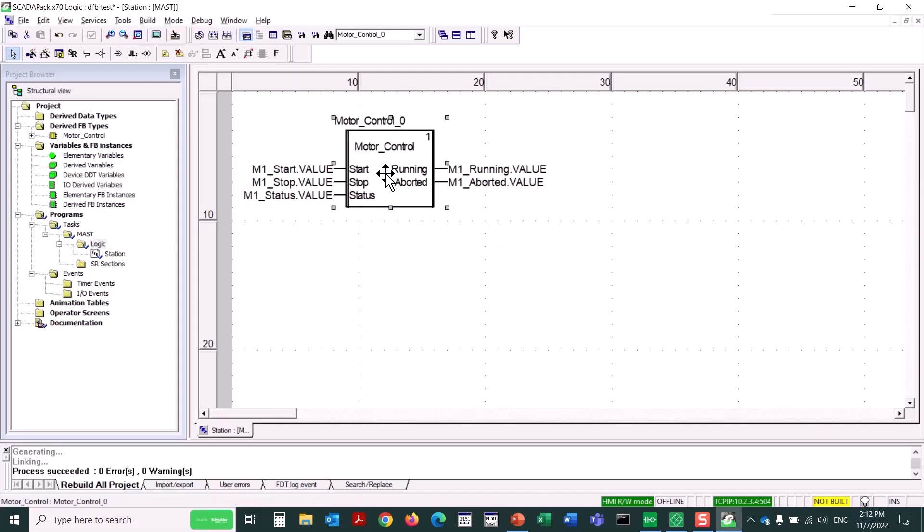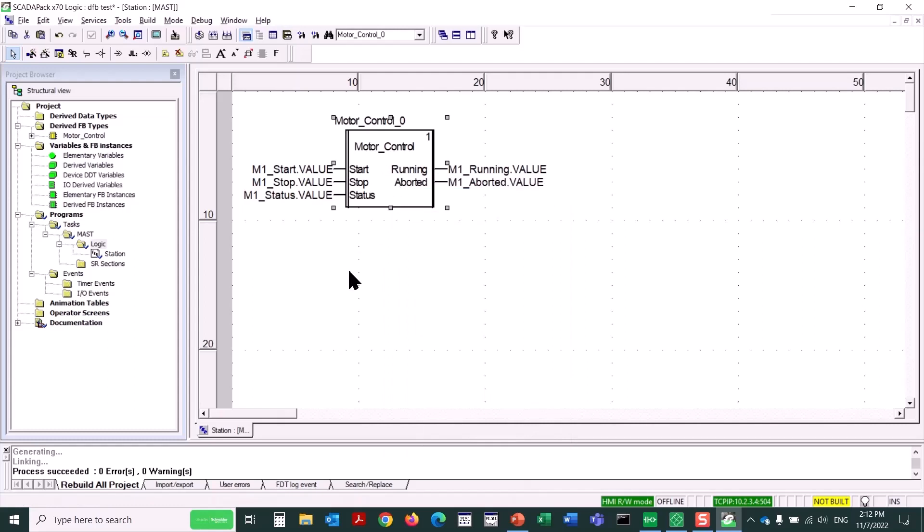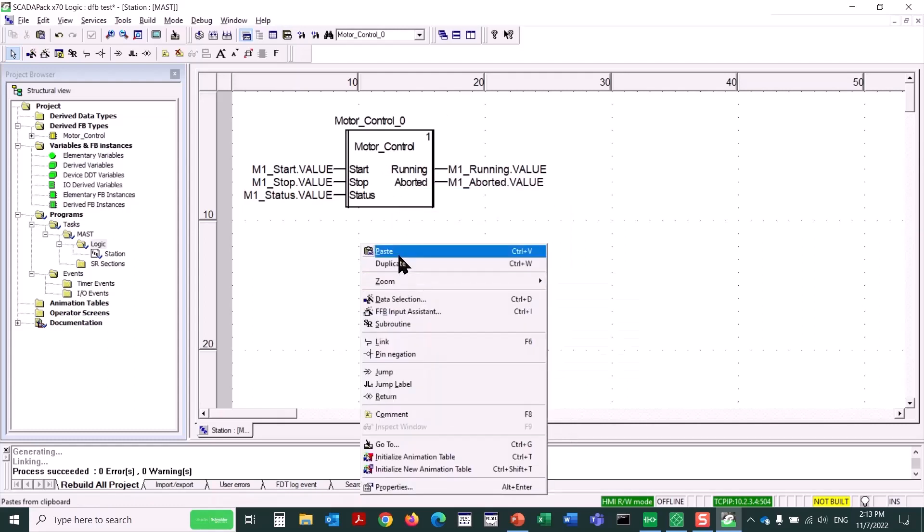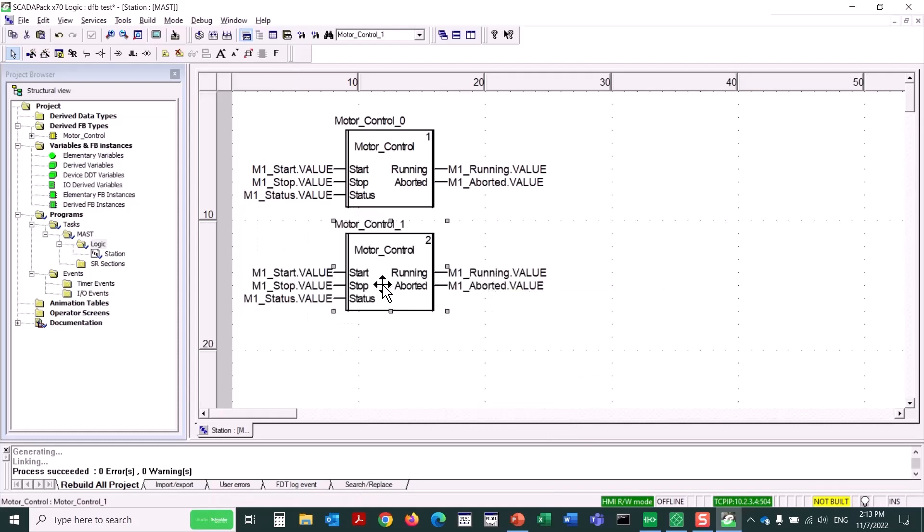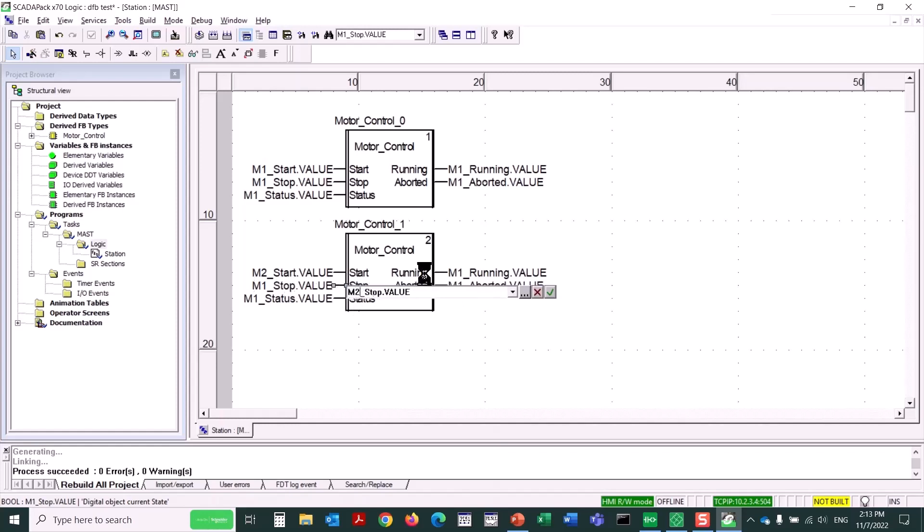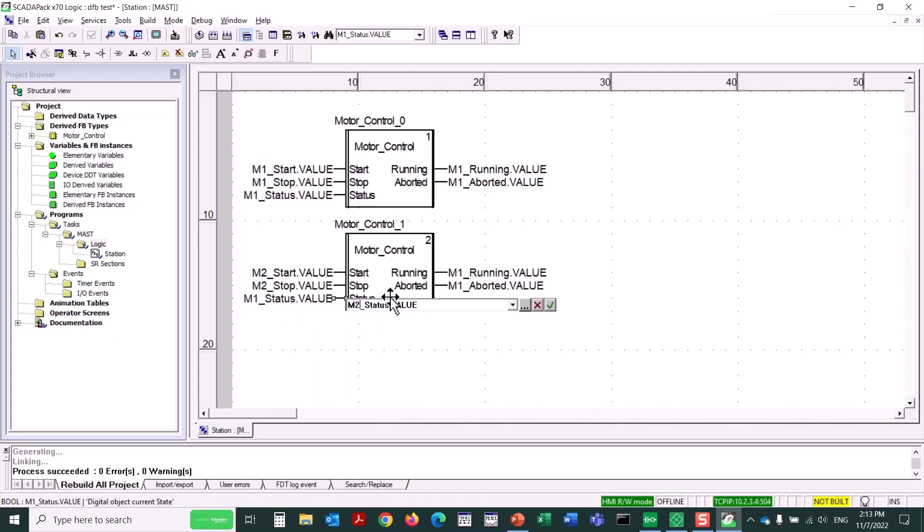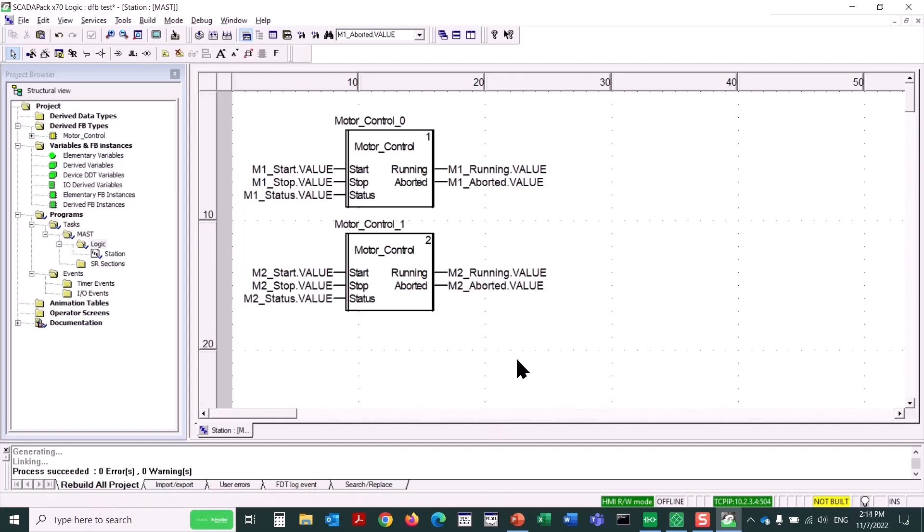But to show you the full value of creating a derived function block, we can simply copy this function block. I can right-click and select copy, or use Ctrl-C, and then I can right-click again and paste, and drop a copy in. There it is. Notice the instance number here is 0, the instance number here is 1. Now, we need to simply change the object names from M1 to M2. It's as simple as that, because we've already created these objects. I'm just double-clicking on the object parameter here, and that opens it so that we can edit. I could have hit the little check mark, but if you just hit enter, it does the same thing.